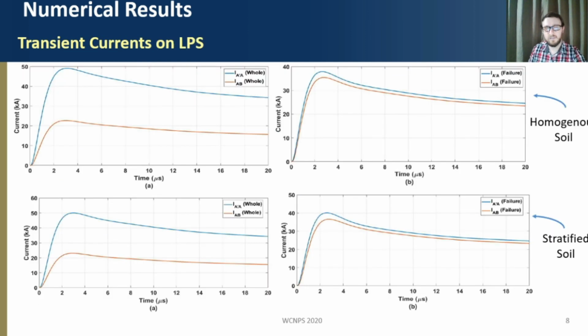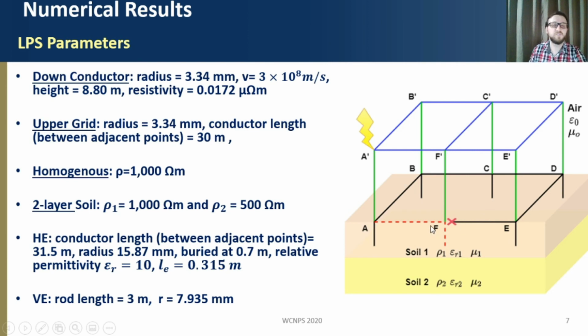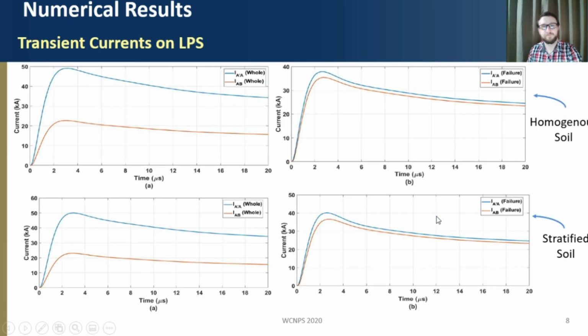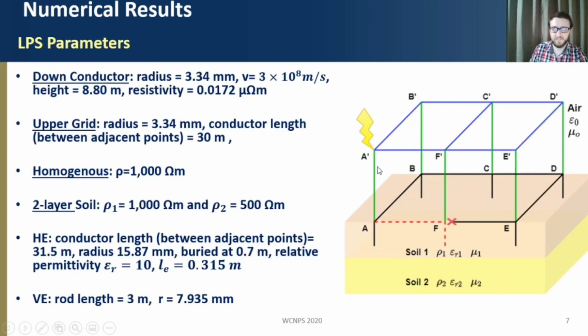Just one thing more: we also consider the whole condition, so there is no rupture in the ground system, and then we apply a rupture, these dashed lines here, where this point is disconnected from the ground system grid. First, we analyze the currents in segments A prime, A and AB. So it would be that current here, and then the other current flowing in that direction, considering the whole system condition and the rupture, the damage.